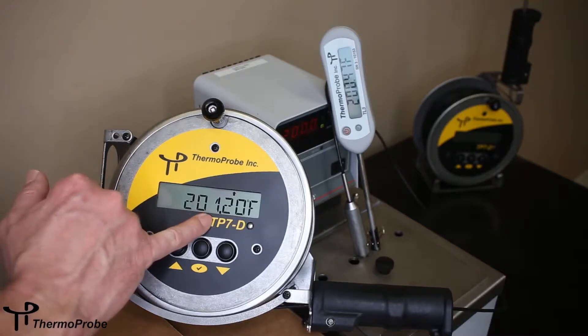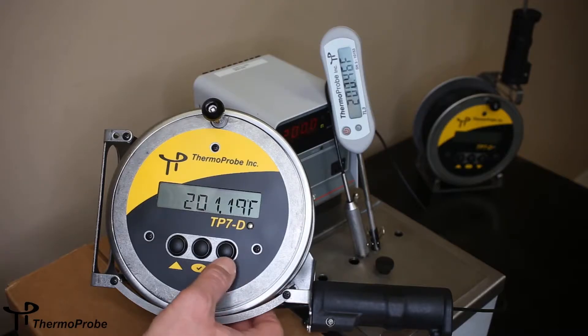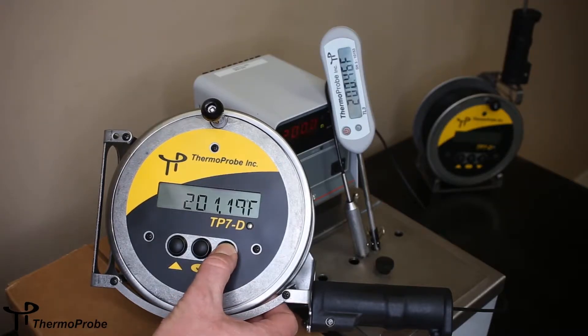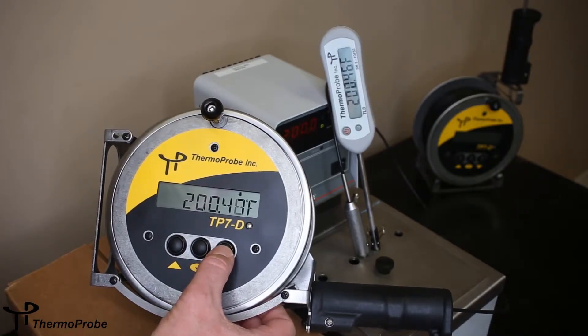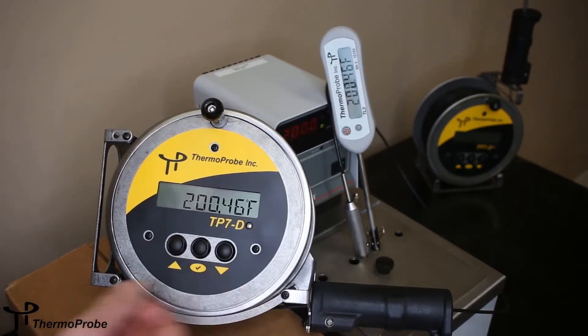Again, we want to adjust the thermometer to read the same as the reference. So, we're looking for 200.46. Bring it down. Down. Four. Six. Four. Four. Yeah, it's at four six.